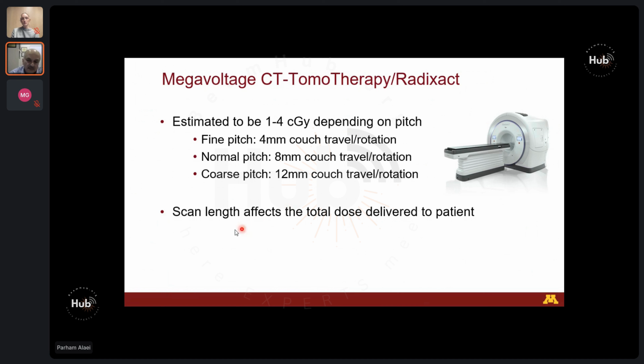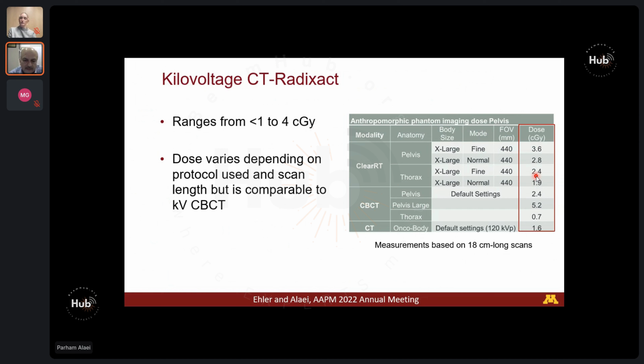The newer Tomo units, which are called Radixact now, do have kilovoltage CT, called ClearRT. The dose from this varies depending on the protocol, but it's comparable to kilovoltage cone-beam CT. So I have some data in here that we collected a couple of years ago. Again, it is in the ballpark of the cone-beam CT on a C-arm LINAC. And then kilovoltage cone-beam CT, which is the bulk of what we use, the dose from that depends heavily on the protocol used. Head and neck protocols in general are low dose, thorax are a bit higher, and the pelvis even higher.